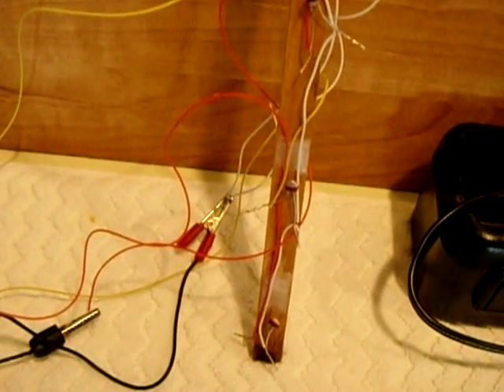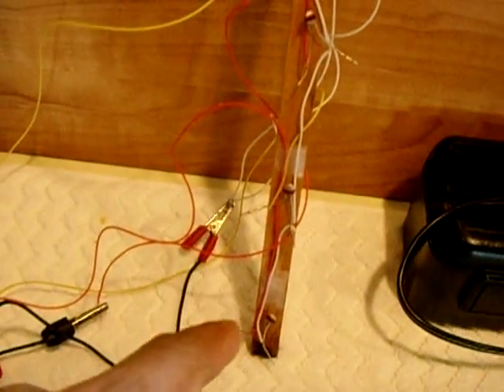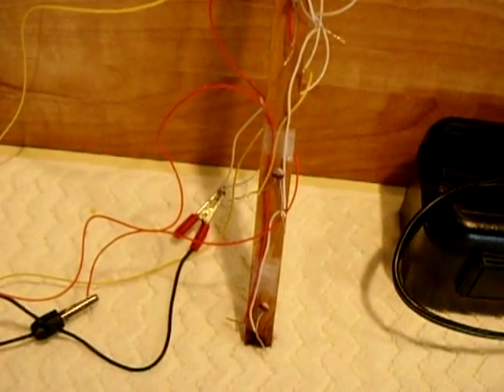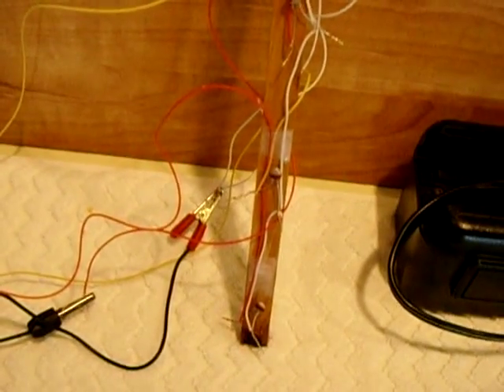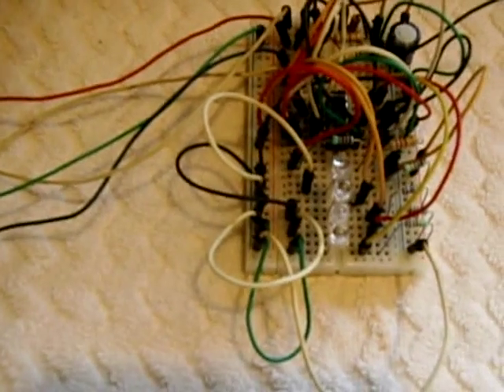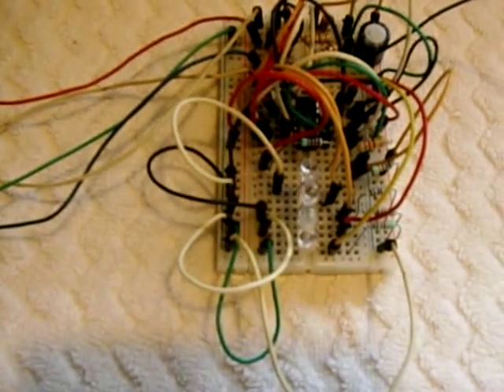That's how it works. It works very well as long as you do a good job with your 22 gauge telephone wire with the heat shrink and the sealant around each thermistor. Take a nice PVC pipe, 1/2 inch. Nylon tie each thermistor in position in the tank and route the wires out to the control box where this circuit will be located, and you will be good to go.